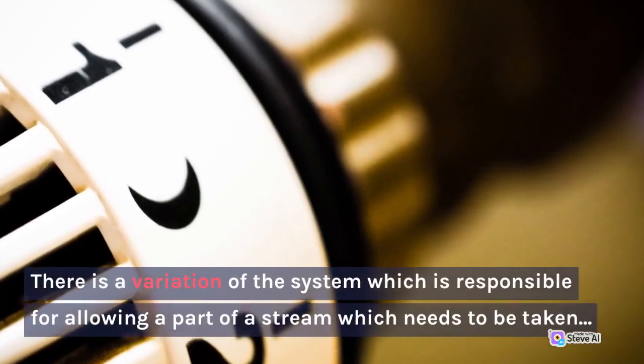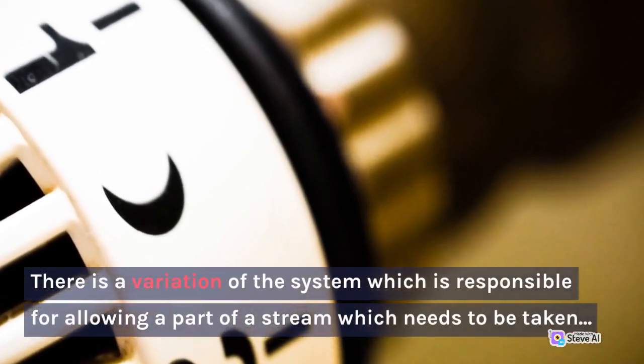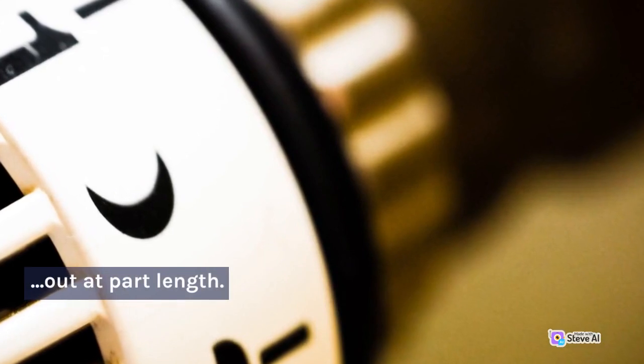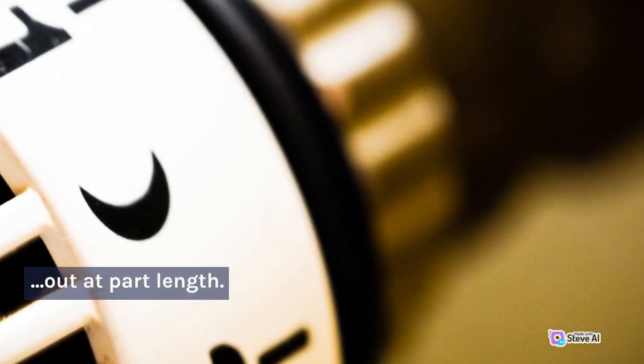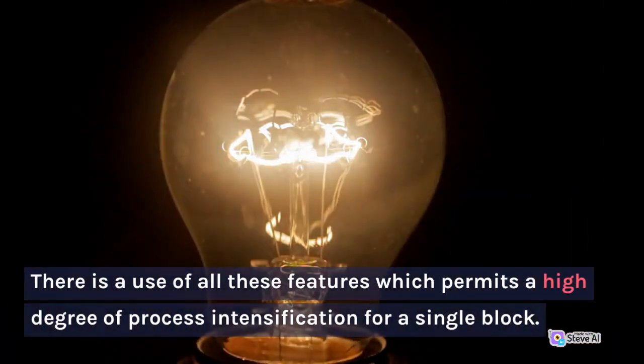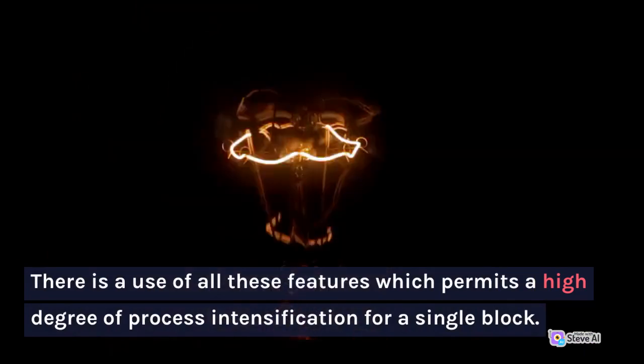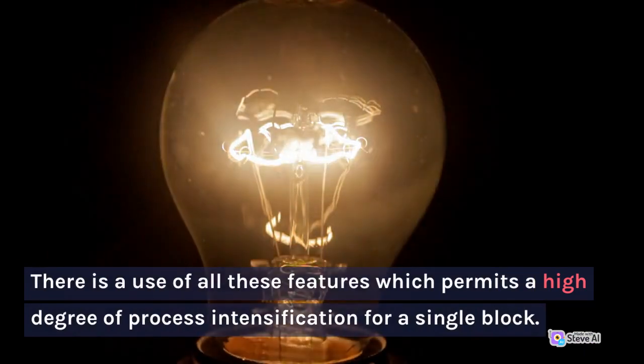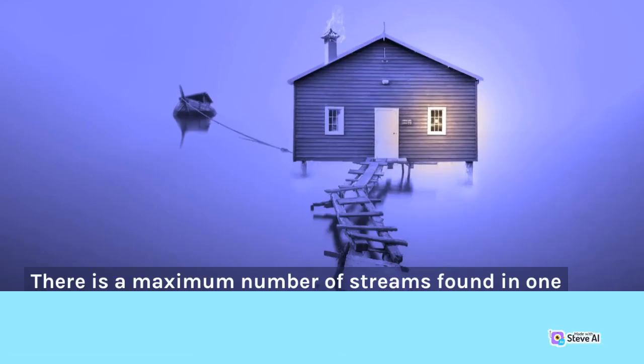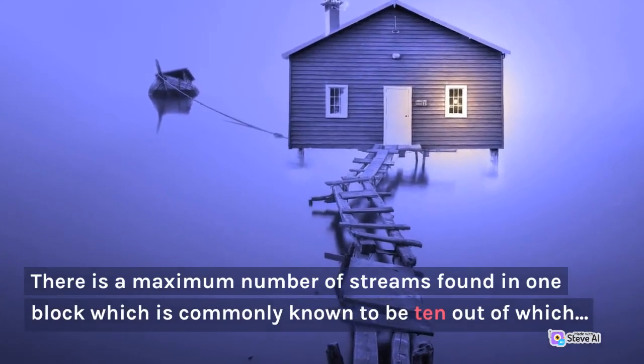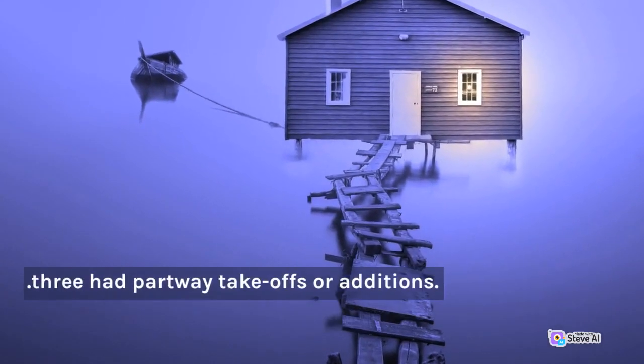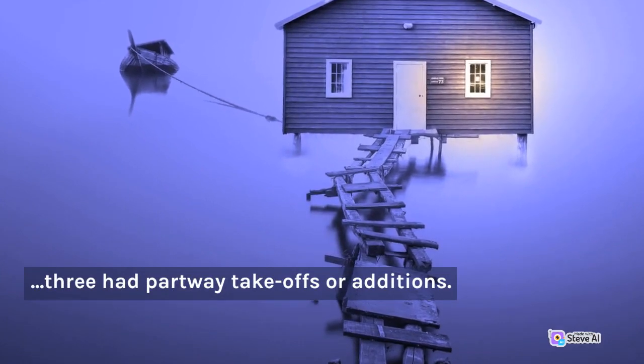There is a variation of the system which allows a part of the stream to be taken out at part length. The use of all these features permits a high degree of process intensification for a single block. The maximum number of streams in one block is commonly 10, of which 3 have partway takeoffs or additions.